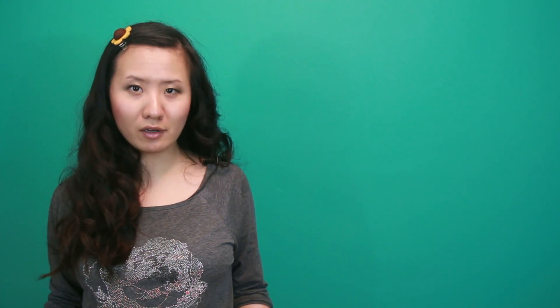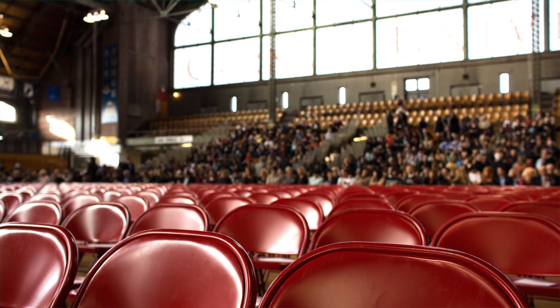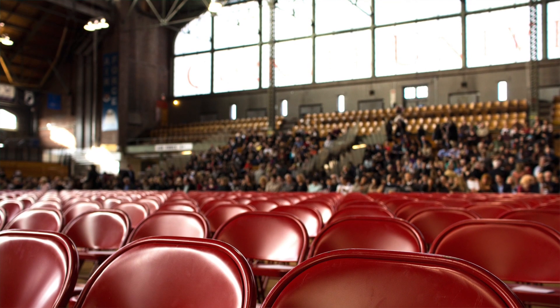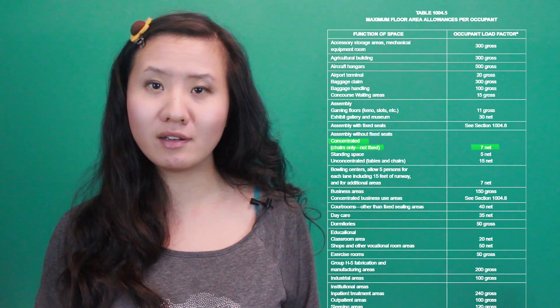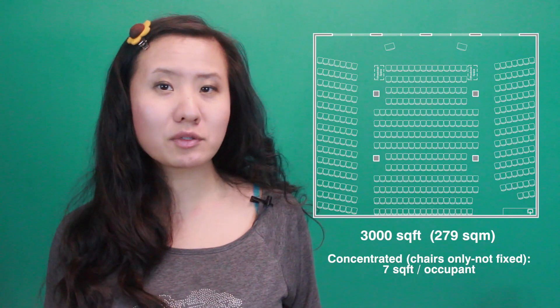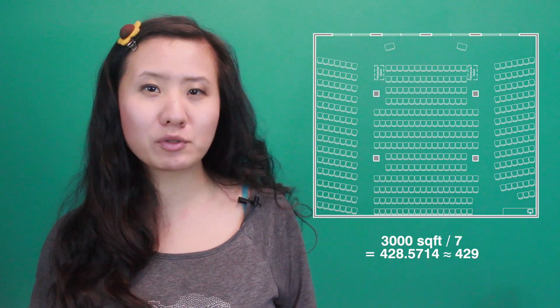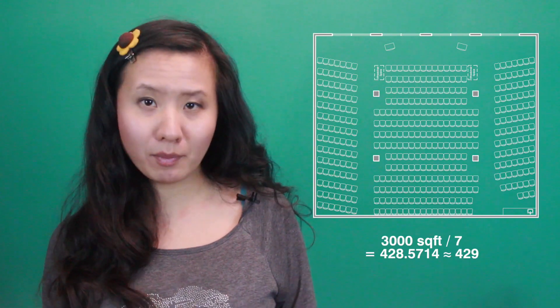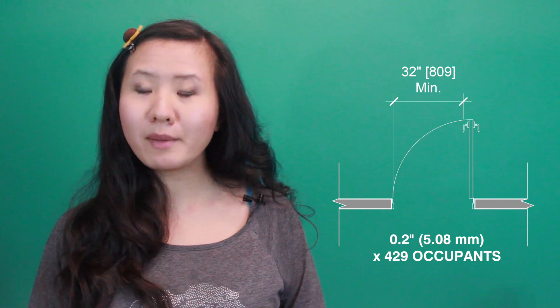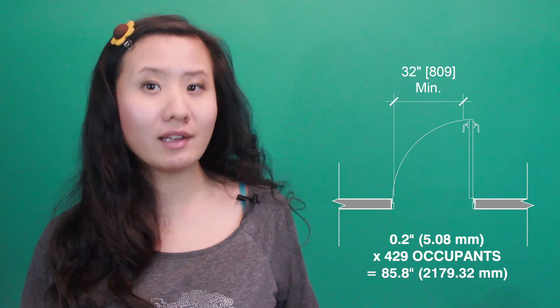Let's take a look at an example with a higher occupant load. For instance, a community meeting room with loose seating. This usage as per the load factor table is listed as 7 square feet per occupant. So in our 3,000 square foot room we could expect 429 people, which when multiplied by 0.2 inches would equal 85.8 inches. Since we definitely need at least two exits or exit access doorways, one way to achieve this is by having two doors, each having a clear width of at least 42.9 inches.